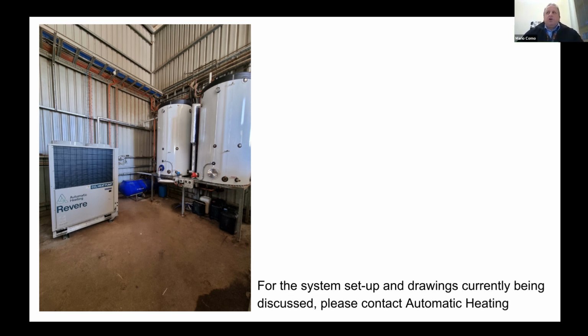So this is the system after the hot water's used, and I'll call it the system off stage. Tank 2 sits at 60 degrees and is full. Tank 1 sits at 83 degrees and is over half the capacity. And we have a solenoid valve in the closed position. So this is basically at the off time. When the system starts to heat, we open up the solenoid valve, and we'll explain why we do that later on.